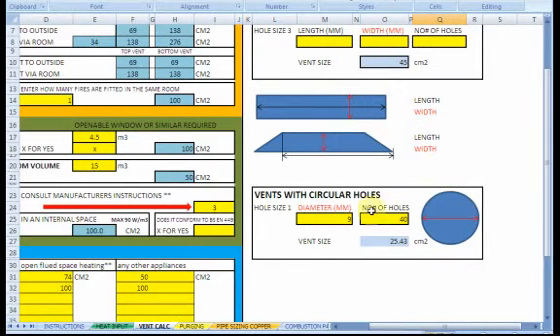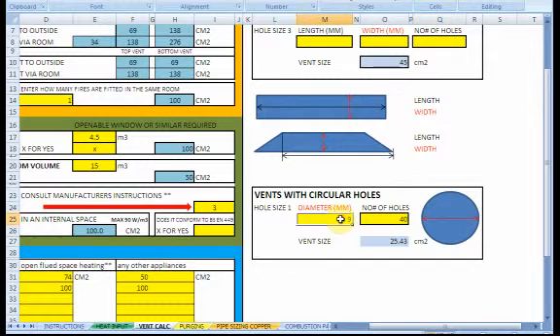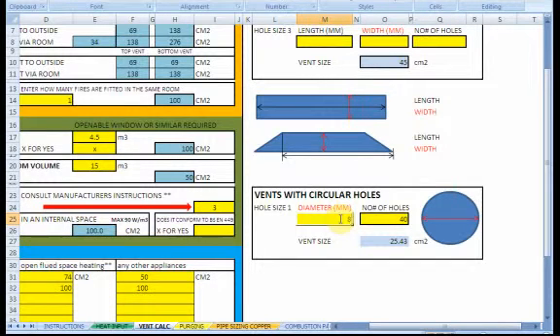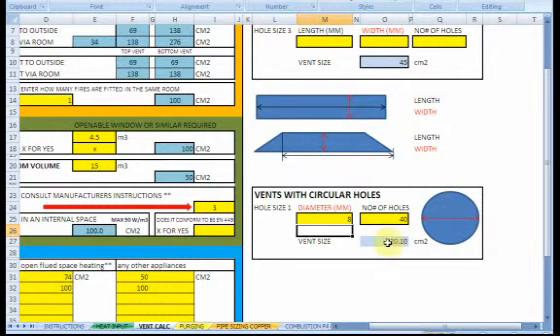If the vents have got circular holes, then we need to know the diameter of the hole in millimetres. And if the diameter is 8 millimetres and there are 40 holes, then the vent is equivalent to 20.1 centimetres squared.